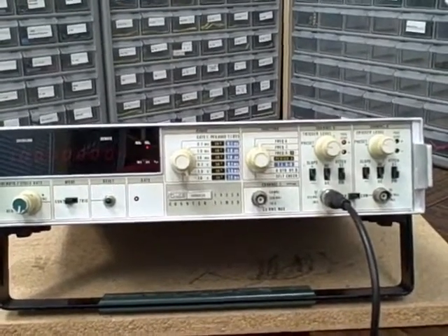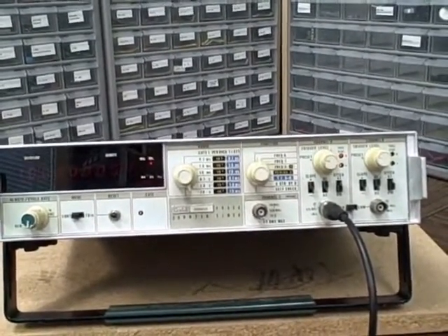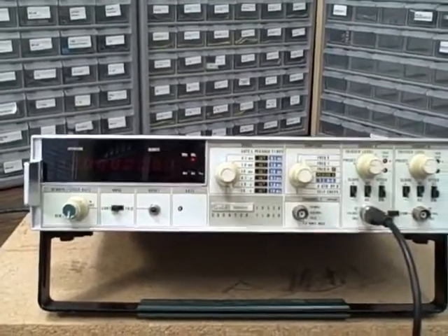So now we'll get back to this 1953A. I think this unit has it all. At the time Fluke came out with it — about 1975 — it had about a 10-year run, because I saw revisions in 1985 to the manual and a number in between. At the time it came out, you can bet this was quite an expensive unit. They introduced a base unit to keep costs down, and the base unit has no options — you would have had channel A and B.